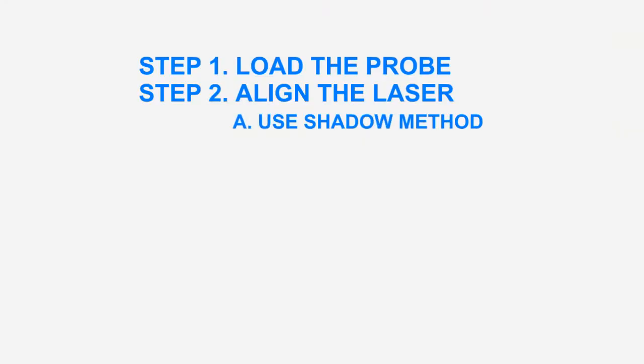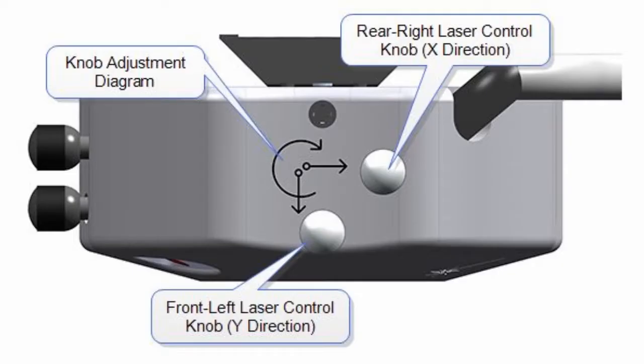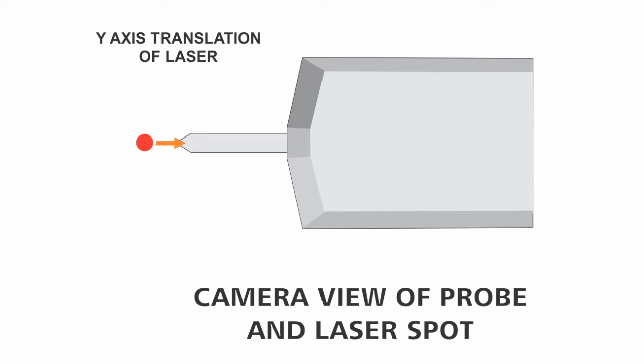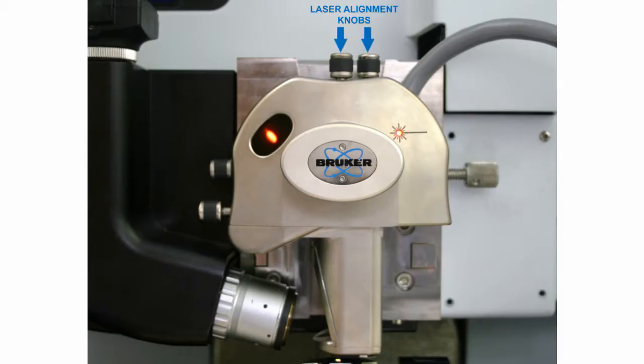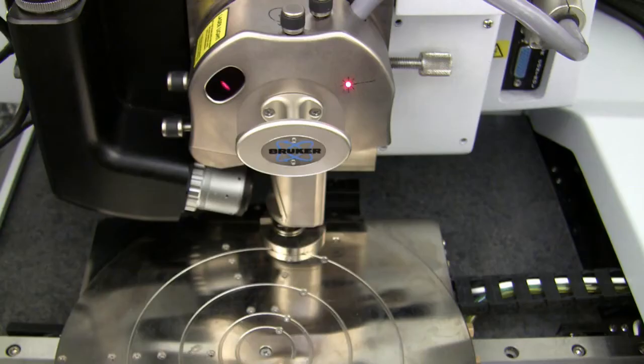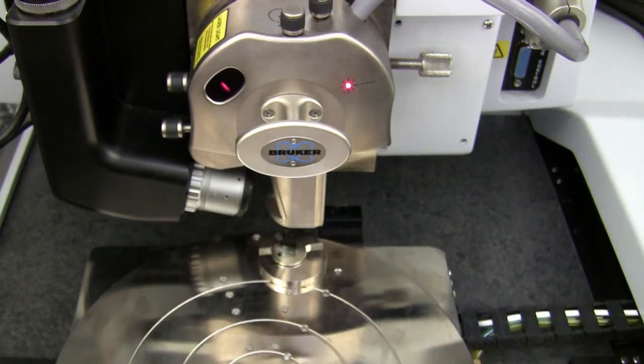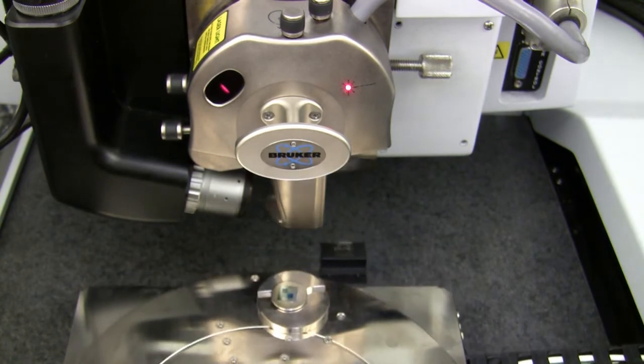There are two methods for aligning the laser onto the probe. Either method can be used to position the beam. The first technique involves projecting the laser onto a surface underneath the head and probe holder to observe the beam as it moves across the cantilever. The two knobs on the top of the dimension head are used to adjust the position of the laser onto the probe cantilever. On the left side of the head, there are two knobs to adjust the reflected beam onto the photodetector. Move the stage forward to allow room for the projected laser beam.